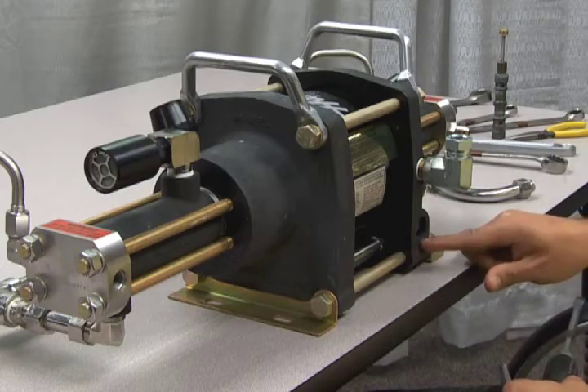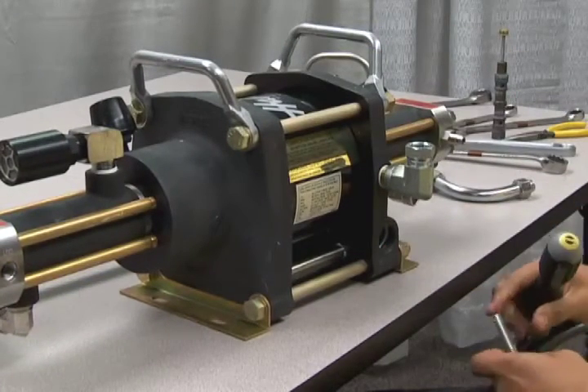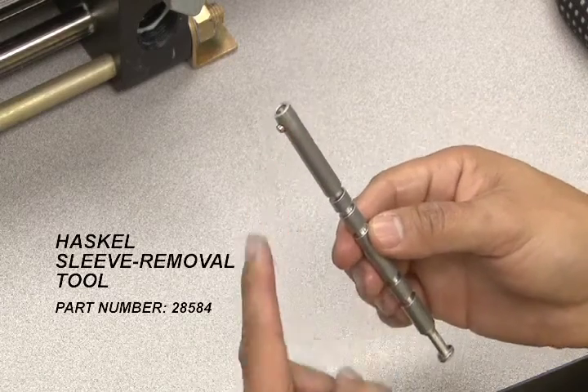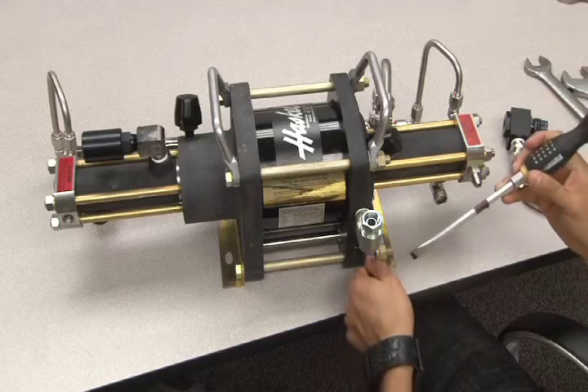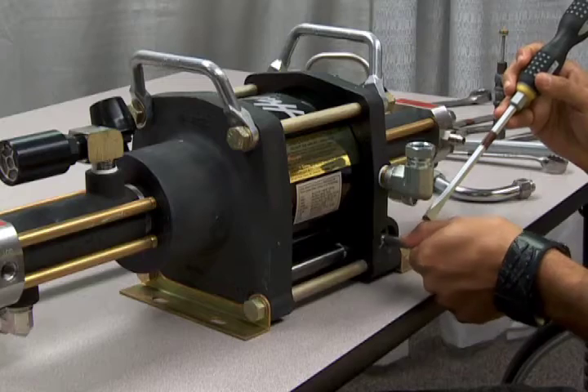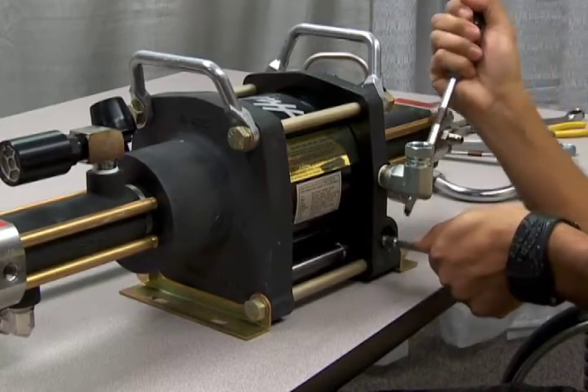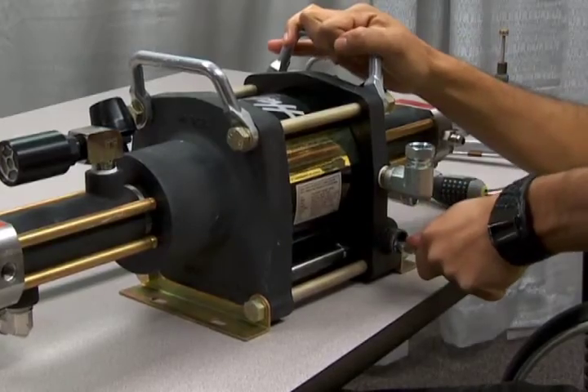When performing a complete reseal of the cycling valve section, it is also necessary to remove the sleeve. This can be done with a small allen wrench and a pair of pliers, but it is much easier to use the Haskel sleeve-removal tool. This tool has a hook at the end and slots on the side, which allow you to use a flathead screwdriver to pry out the sleeve. Insert the tool into the sleeve and feel for it to grab the sleeve inside. Once you feel it grab, insert a flathead screwdriver into one of the slots on the tool and leverage it against the unit's body to pry the sleeve out.